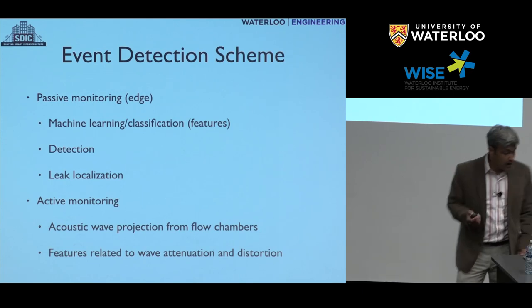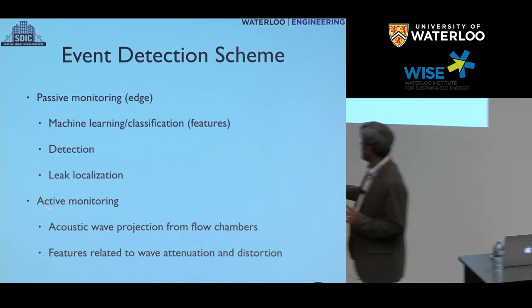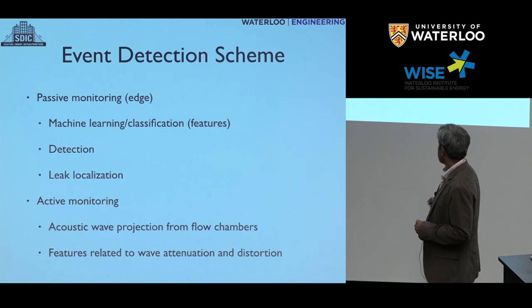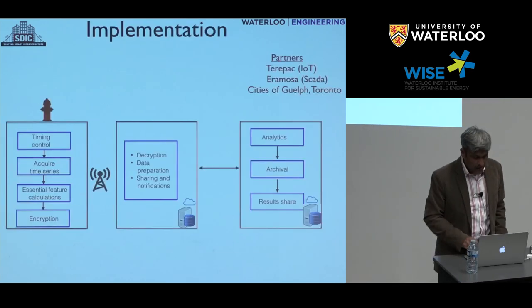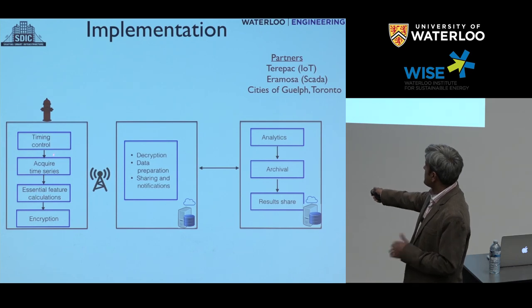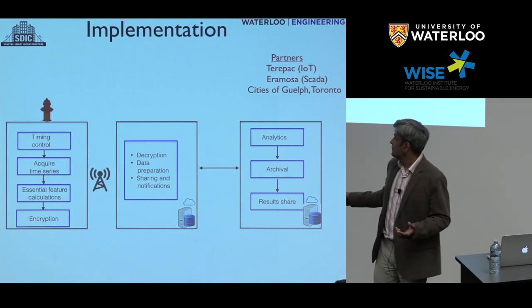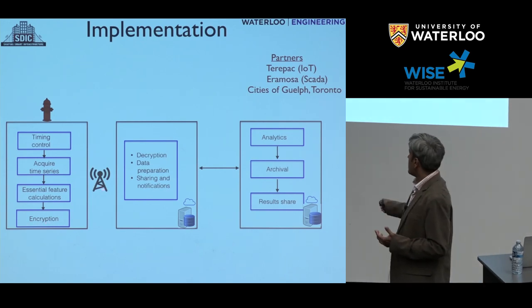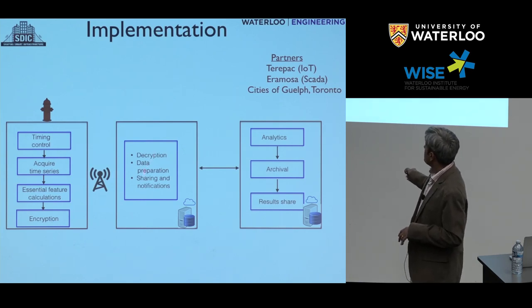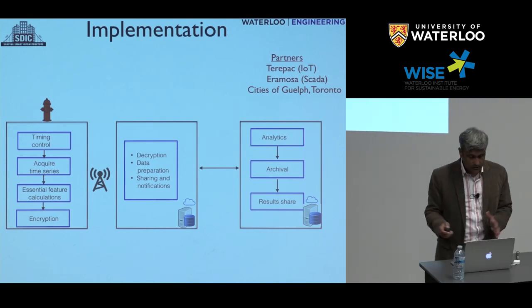There are lots of tests being done in the hydraulics lab: passive monitoring with machine learning classification, detection, and localization. We are also looking at active monitoring using sonar principles to localize leaks, as well as wave attenuation and distortion. The intelligent edge at the hydrant handles timing control, time series acquisition, feature calculations, and encryption — with cellular connectivity for data sharing and notifications. Feature extraction uses standard machine learning with frequency peaks, root mean square, and the Bhattacharyya distance that looks at distances between two histograms. Those types of features give you an idea whether there is a leak occurring.